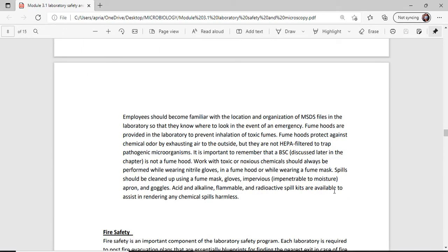Your employees should be familiar with the location and organization of MSDS files in the laboratory so they know where to look in case of emergency. Fume hoods are provided in the laboratory to prevent inhalation of toxic fumes. Fume hoods protect against chemical odor by exhausting air to the outside, but they are not HEPA filtered and do not trap pathologic microorganisms - they only target fumes, not microorganisms or pathogens. It's important to remember that BSCs, which will be discussed in later chapters, are not fume hoods.